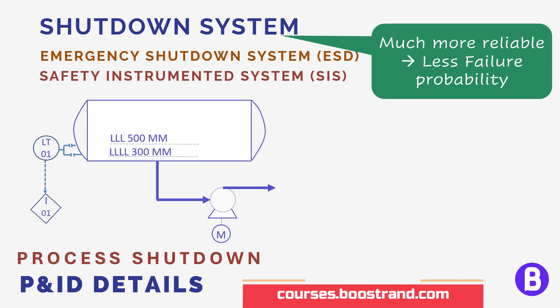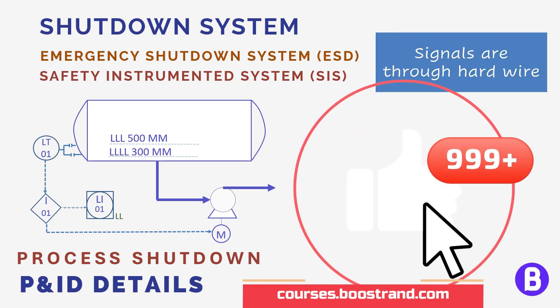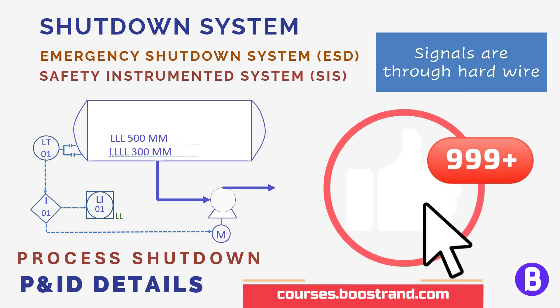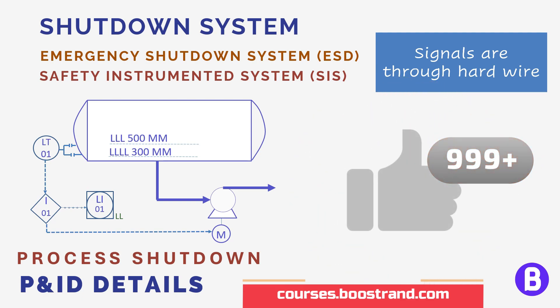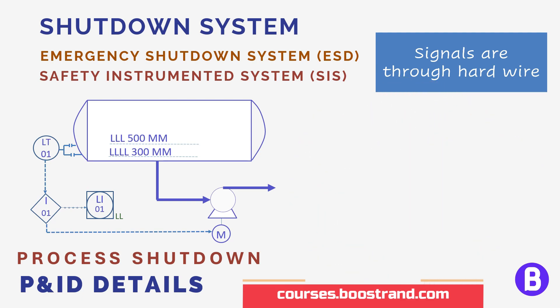The shutdown system shall stop the pump. We can still send an indication to the operator in the DCS, along with a low level or low-low level alarm. Here, the type of signal is different — it's not a serial link, as we need a more reliable signal. That's why a hardwire signal is used.